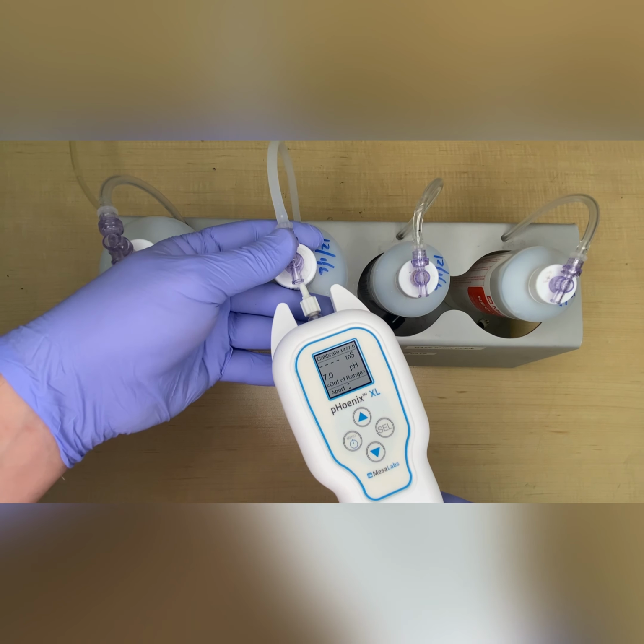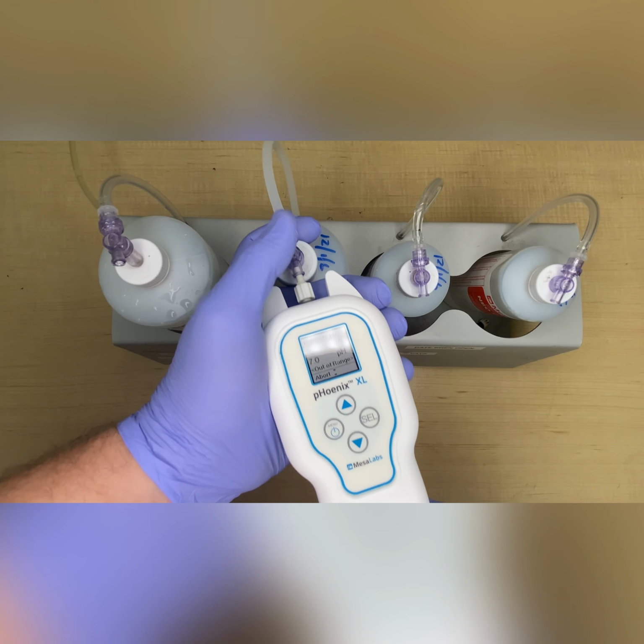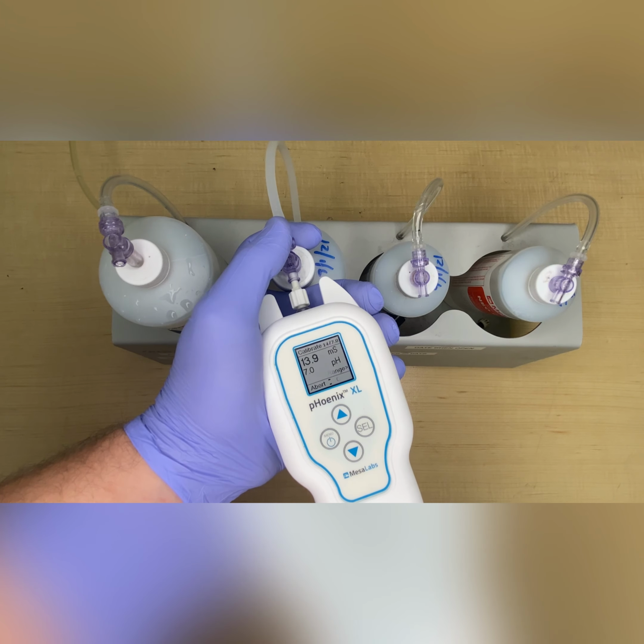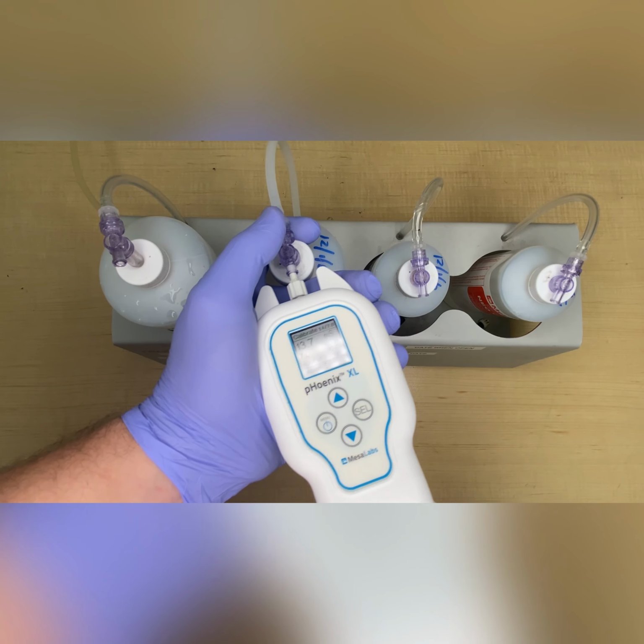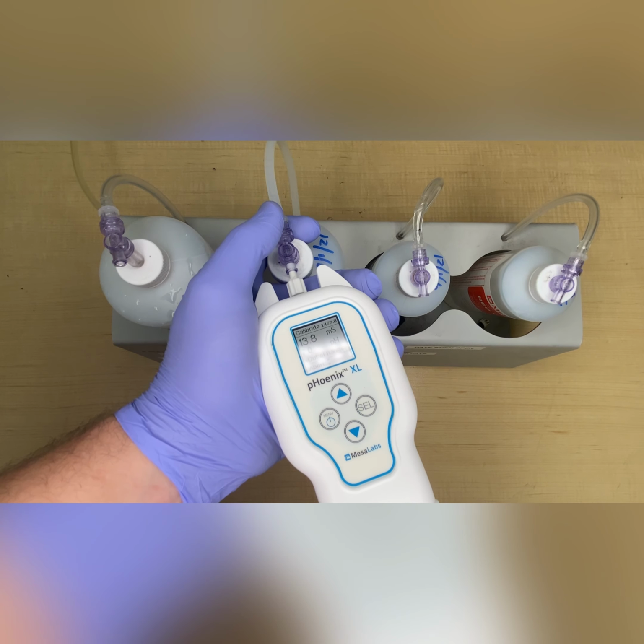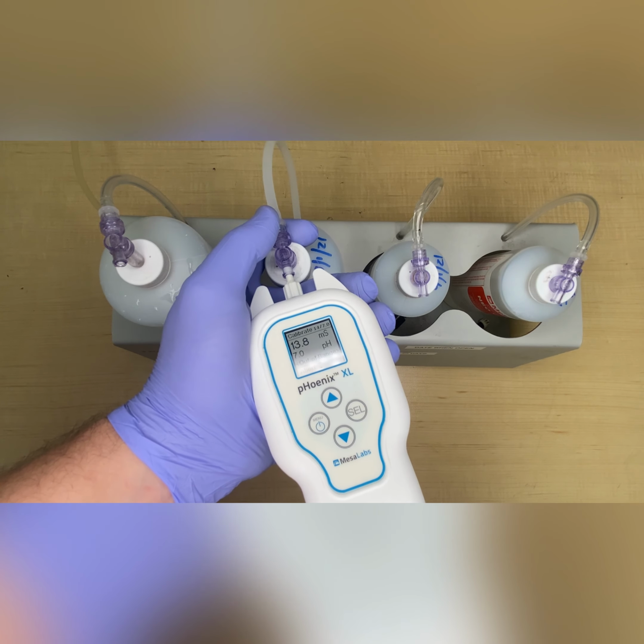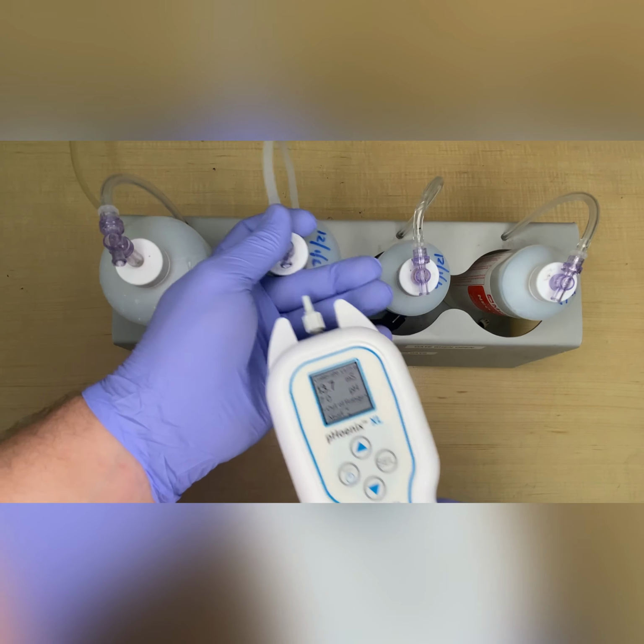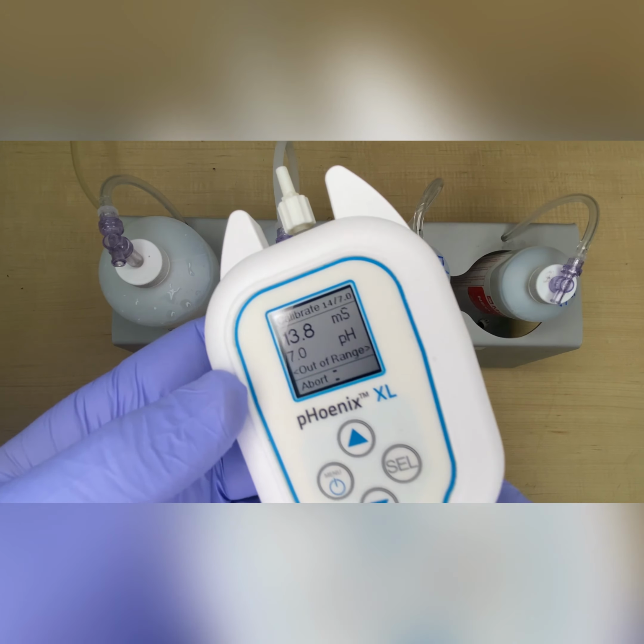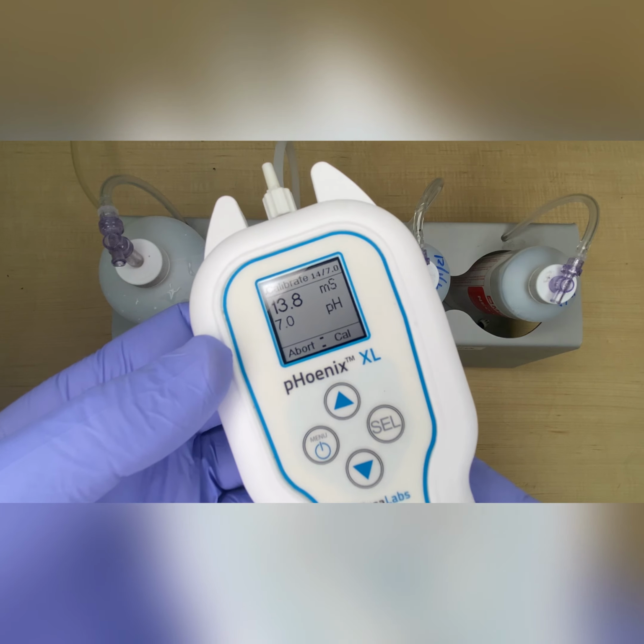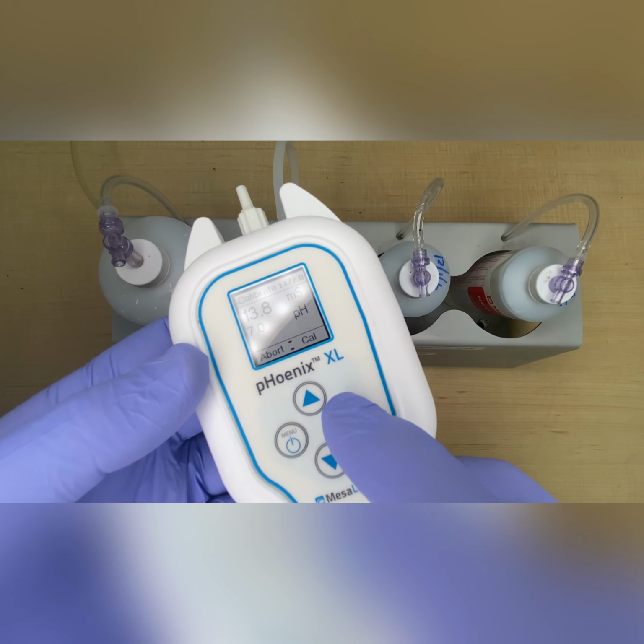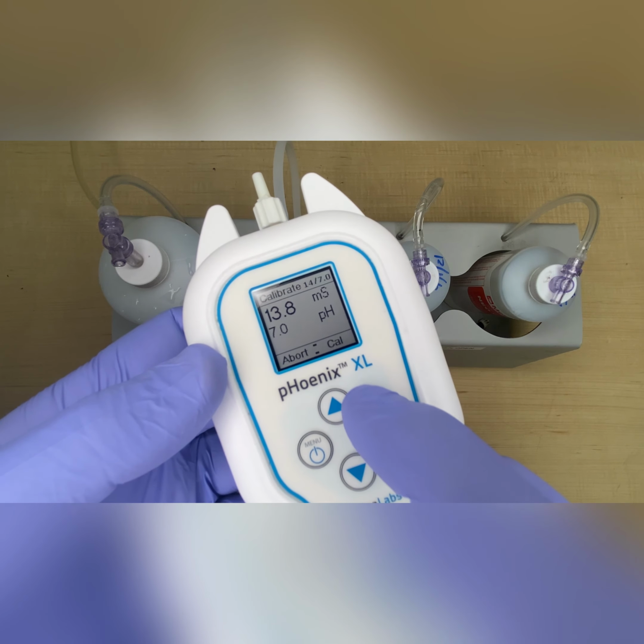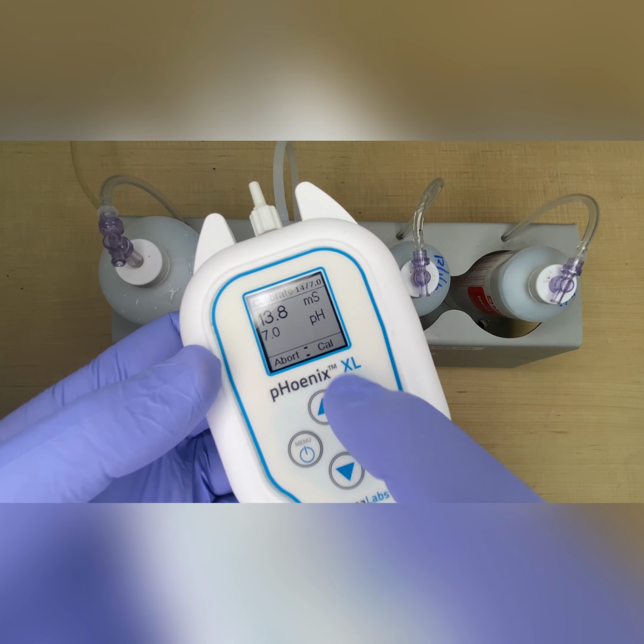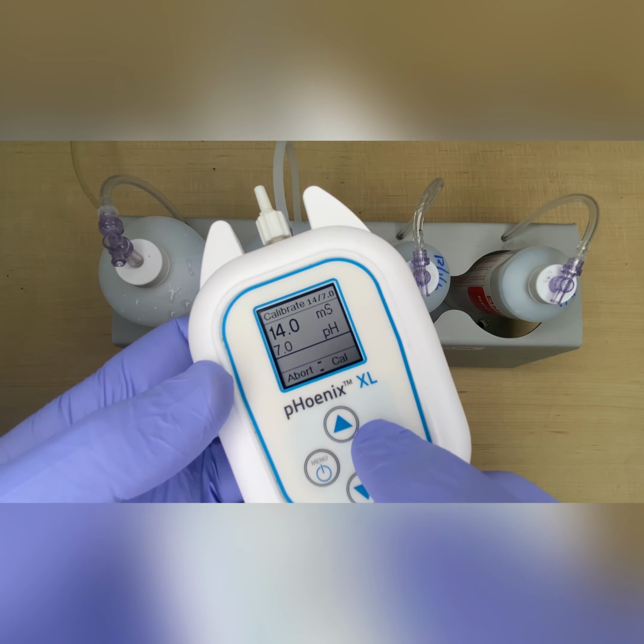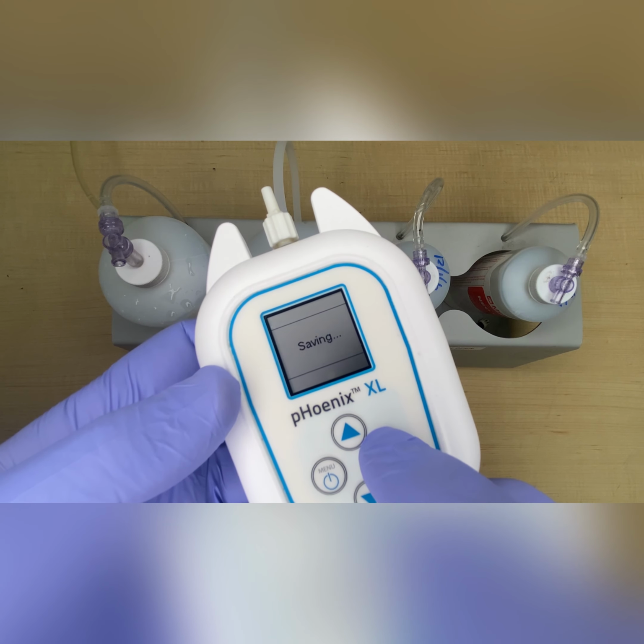Once you've got that rinsed out and you're in the calibration menu, you're going to go ahead and pull your solution through. You want to pull it through a couple of times and get it flushed out. Make sure you don't have any air bubbles in there. What you're looking for on the screen is for the little cal key to come up at the bottom of the screen. That means that it accepted the conductivity solution range. So when that comes up, you just want to hit select, and that's going to save your calibrations.